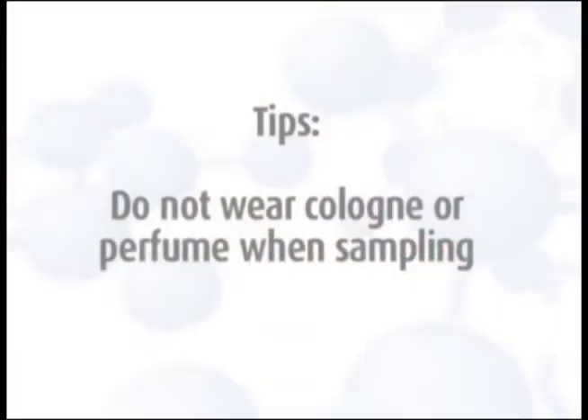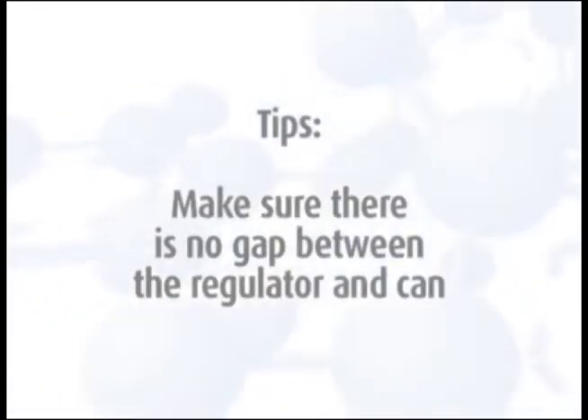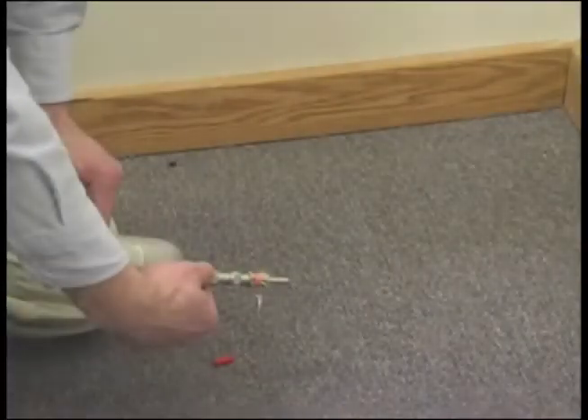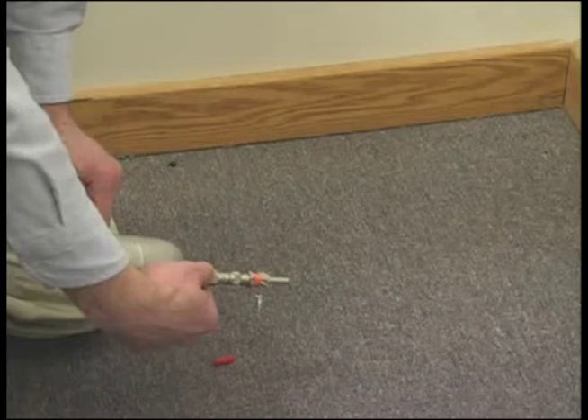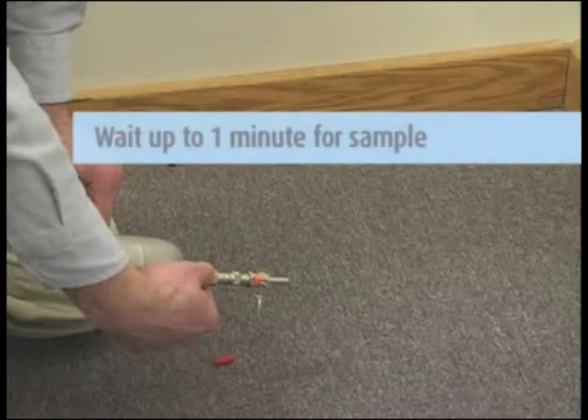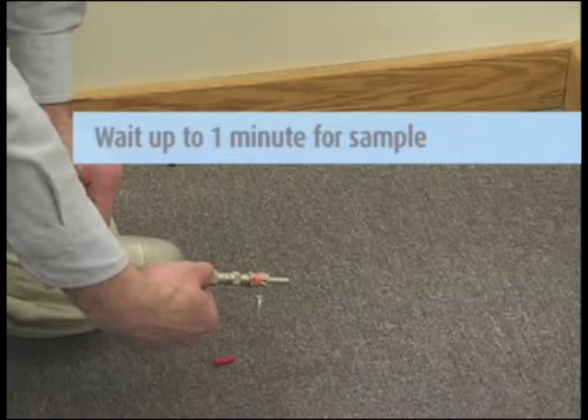Tips: Do not wear cologne or perfume when you perform the sampling. It could interfere with the sample results. Make sure there is no gap between the regulator and can. If there is, the regulator is not seated and you will need to remove and reposition the regulator. You may or may not hear the vacuum pulling in the sample. This will take 20 to 30 seconds to complete. Wait one minute to be sure the sample collection is complete.